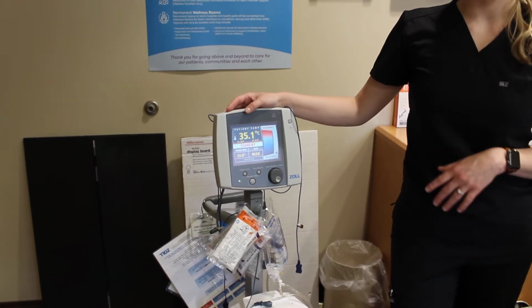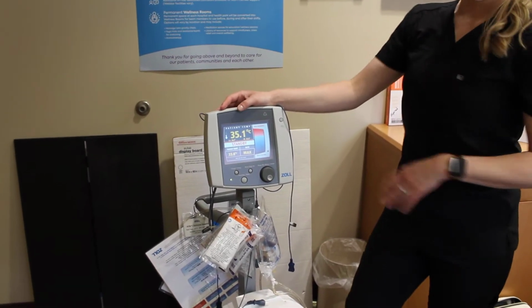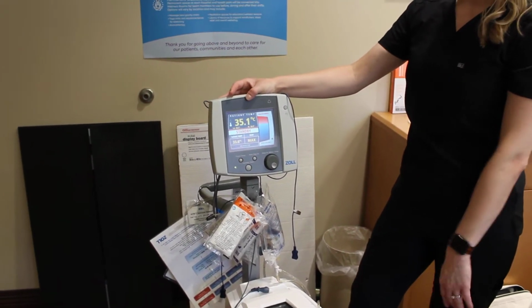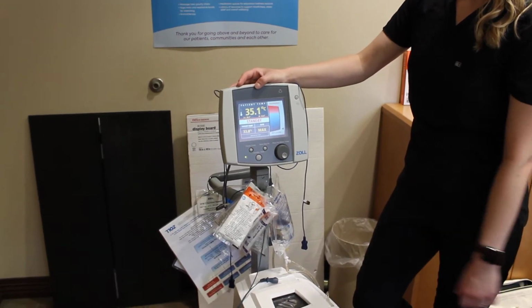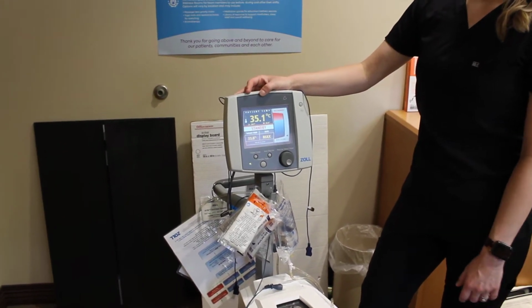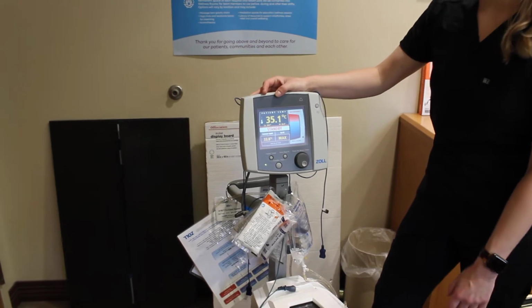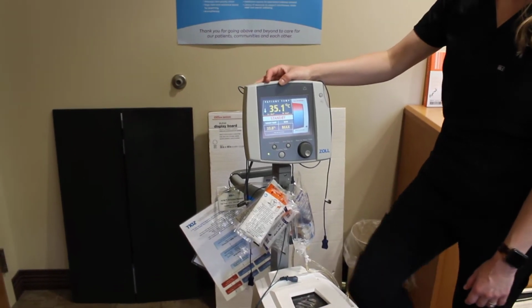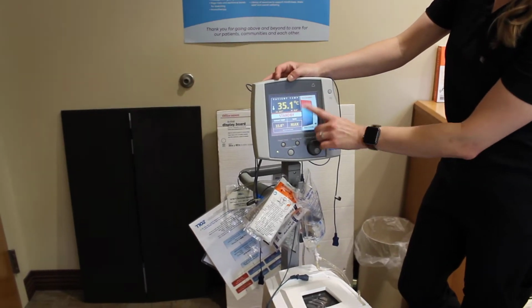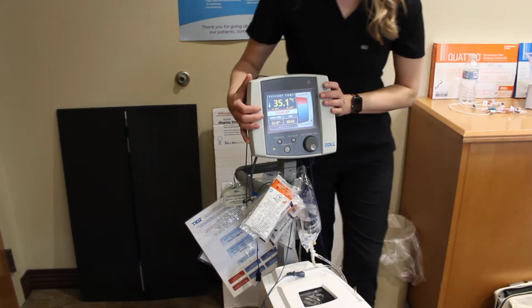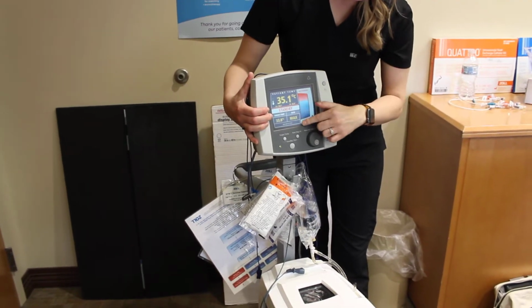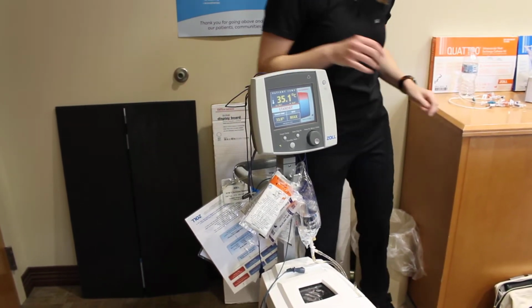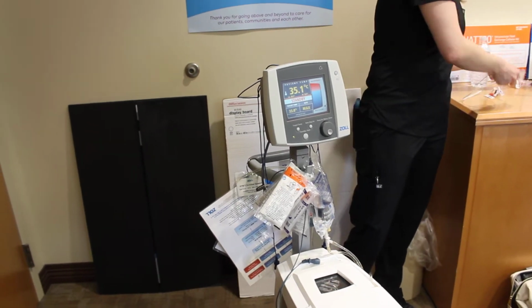Completely done, you just want to make sure your patient doesn't have a fever. The machine's not doing anything, but it's still hooked up. If you wanted to set your high alarm to like 38 or 39, you could do that. It may vary depending on what you want in each case. So we can see it is on standby. You can see our target temp is set to 33. We're set to max mode. So we are ready to hook our patient up.